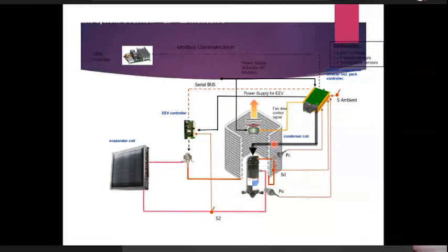And all that is a lot of work for engineers to look at all these varying conditions and then test the product. So not just the simulation part or the design part, but also devise the test method so that we can be sure that if we design it for, let's say, 30% part load, then at 30% we should be able to run the unit. Not that most of the time we find it overloaded because the suction pressure has gone up, and that would be defeating the purpose of design. So if it is designed for 30%, it should operate reliably. For field conditions leading to some choking of the evaporator coil or anything else, we would have the safeties and the ability to switch off the unit.